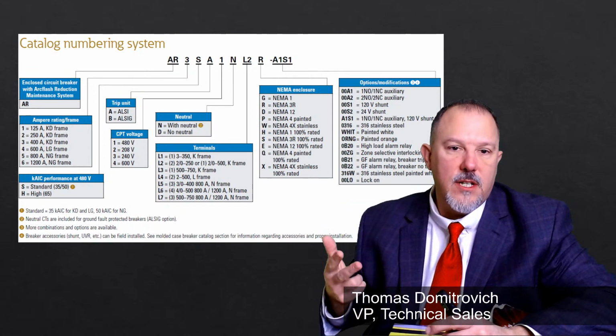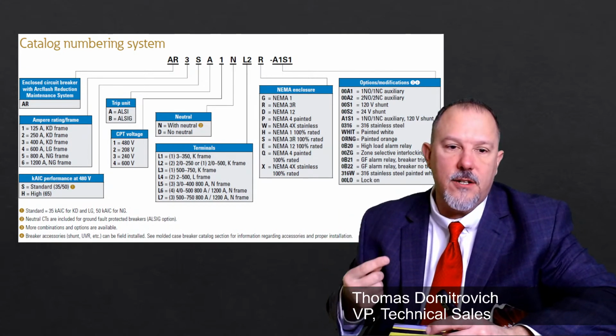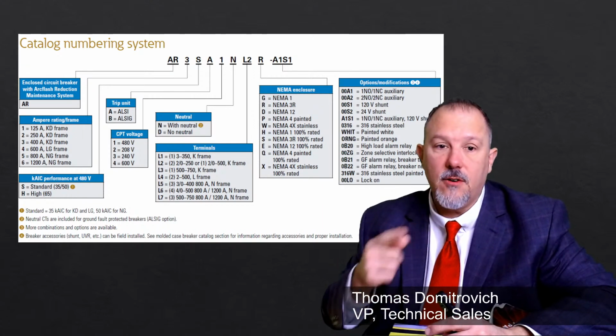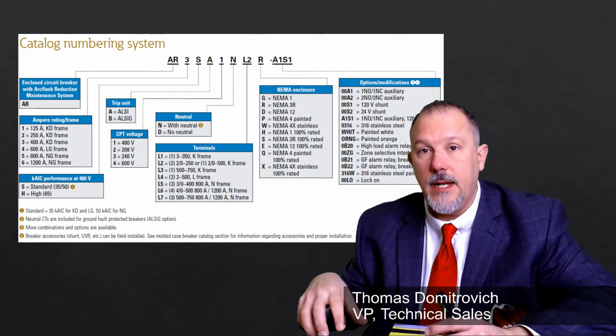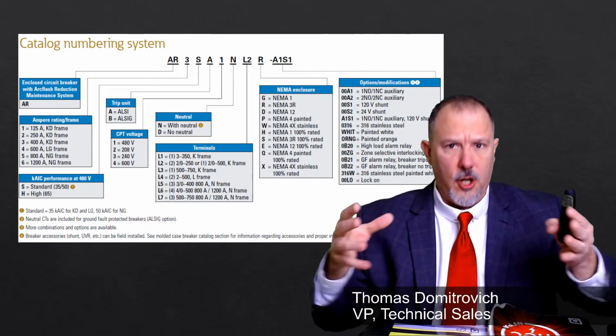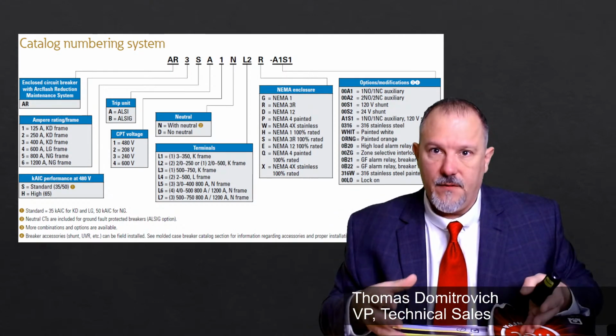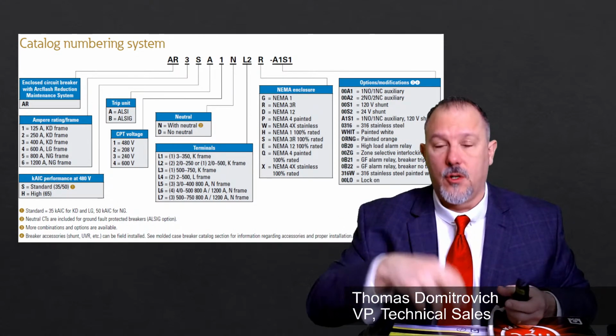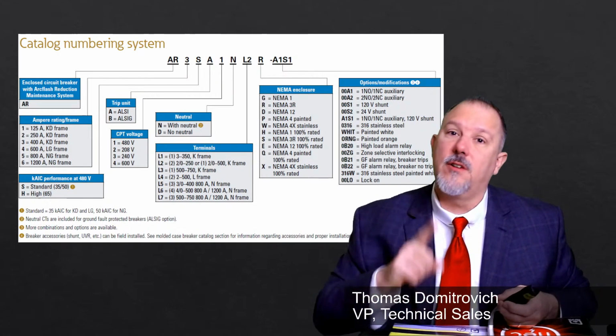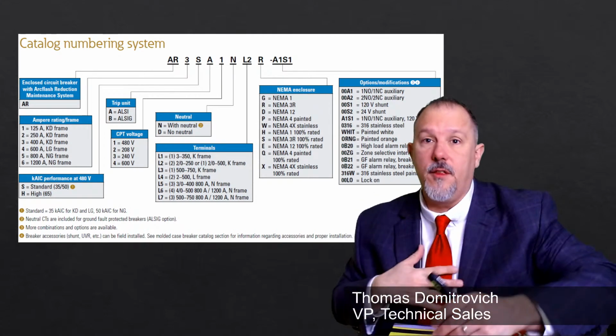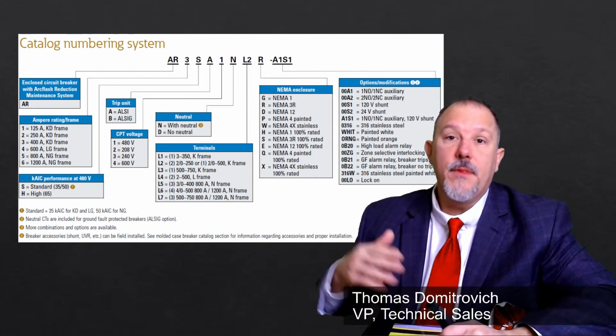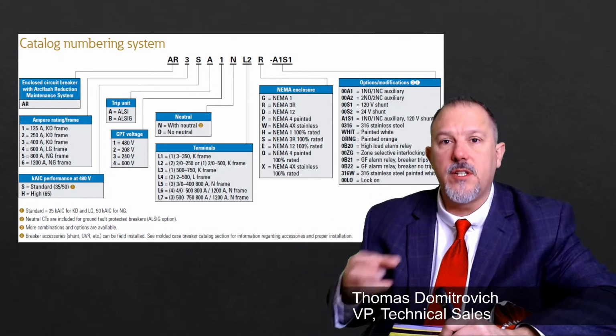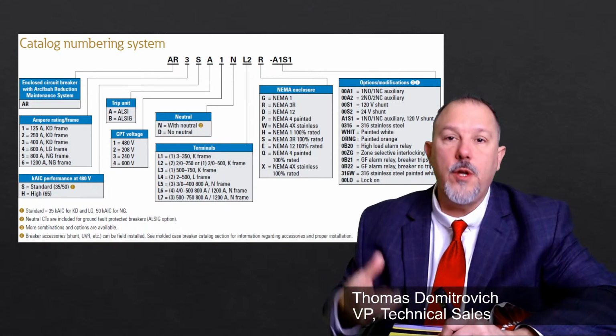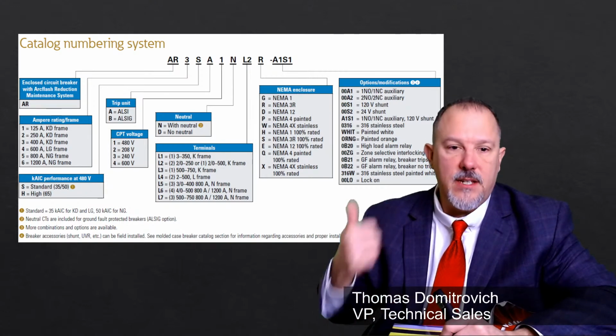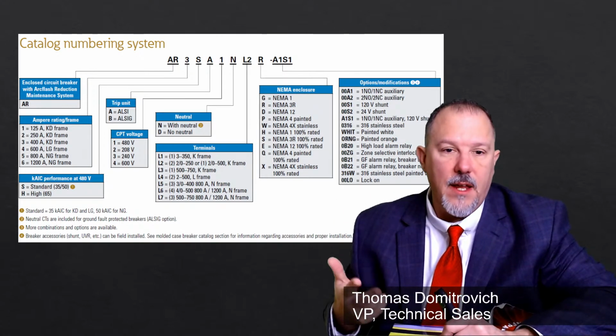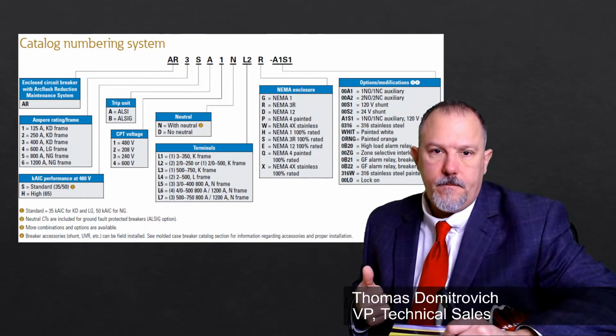The S tells you that it is a standard. You can have a high or standard. That is the short circuit current rating. And remember, since this is an enclosed overcurrent protective device, the short circuit current rating is going to be the interrupting rating, but not in all cases is that true. So we've gone through the steps to make sure that all the different components, any of the power distribution blocks, anything that we use in there has a 65K, 35, or a 50K short circuit current rating.